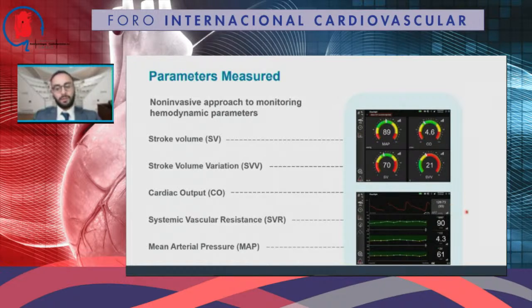The unique thing about this device is that you can actually slave it to your own monitor. It has the same connections that a standard invasive radial arterial transducer would have, very similar connection. We actually were able to do that, and that was an added bonus because we're able to slave all of this information onto our existing monitors, which then go into our electronic medical record.